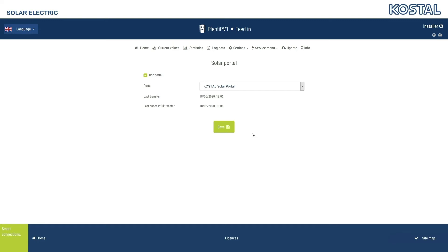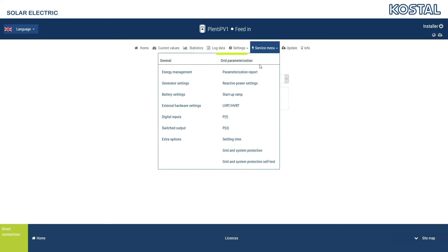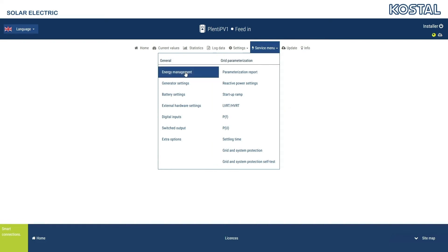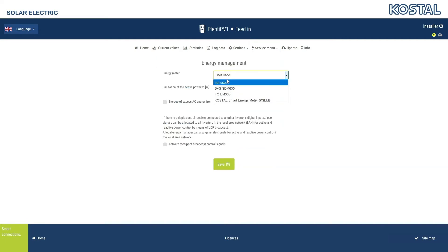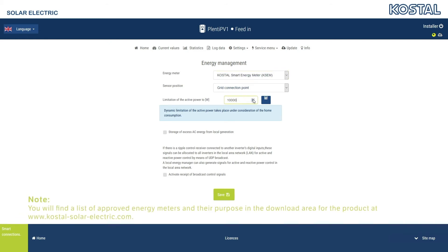More options for configuring the inverter can be found in the Service menu. This is split into General Settings and Settings for Grid Parameterization. If you are using an energy meter, you can select the meter fitted from the overview in the Energy Management menu item, and select the feeding capacity to the public grid. The power is already preset to maximum AC power.